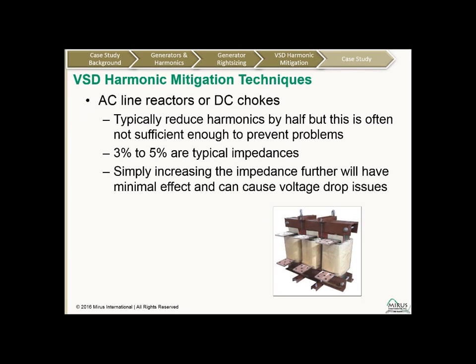3 to 5% are typical impedance levels. If you try to go above 5%, the improvement or reduction is minimal, but you also will introduce additional voltage drop. Drive manufacturers recommend 5% as the maximum. A 5% impedance line reactor is going to introduce a 5% voltage drop at full load. And so if we introduce more impedance than that, then we start having drive-related issues due to the voltage drop.